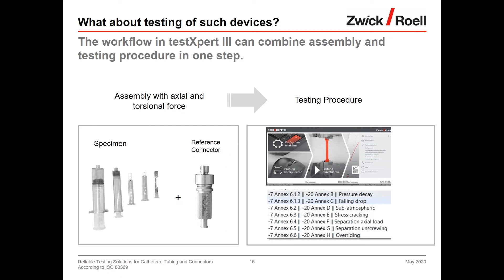The Zwicki line with a superimposed torsion drive can handle the assembly process of the connectors. An integrated air pressure control system is able to handle up to 330 kilopascal and also a negative pressure down to minus 88 kilopascal. Everything is totally integrated in our system. After starting the process, there is nothing to do for the operator. The test machine controls all process parameters, including the integrated air pressure system.